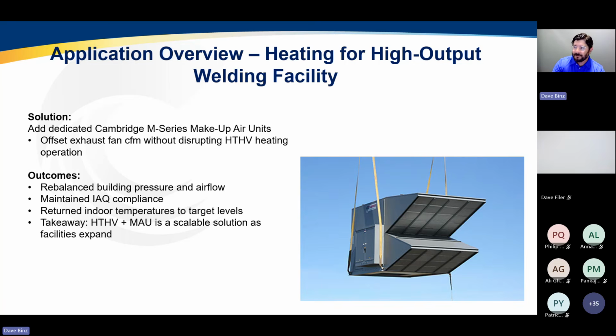And so instead of adding just straight heating, we didn't want to add a lot of Band-Aids to these symptoms throughout the perimeter of the building. We want to make sure we've got an adequate ventilation strategy. So we added some dedicated variable volume makeup air systems. These automated process lines had variable ventilation needs. And so, adding a large amount of makeup air, we want to make sure that the makeup air solution could match my exhaust rate.